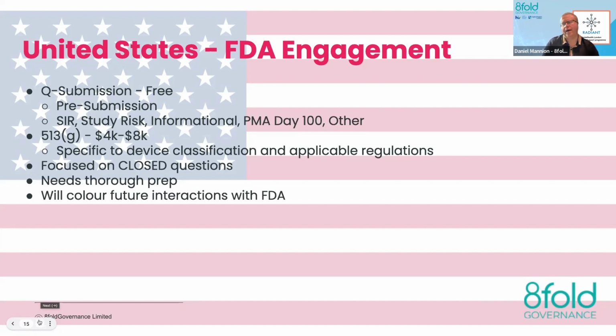There are also other types of Q submissions. If you're doing a more advanced PMA submission to the FDA, which we'll come to in a minute, there's a Q submission to request a meeting after 100 days to review how the progress is going. So Q submission is the FDA catch-all term for all the different free ways that you can interact with us. Pre-submission is the specific Q submission mechanism to ask questions prior to submitting an application for a medical device.